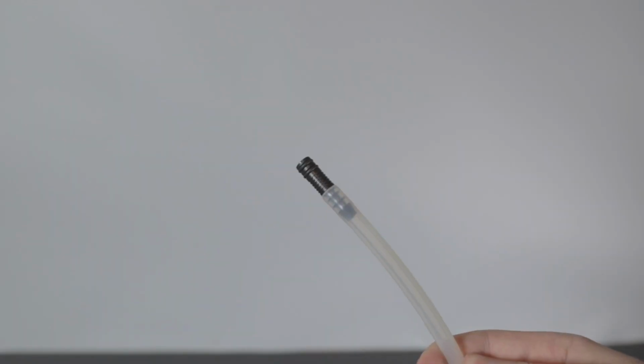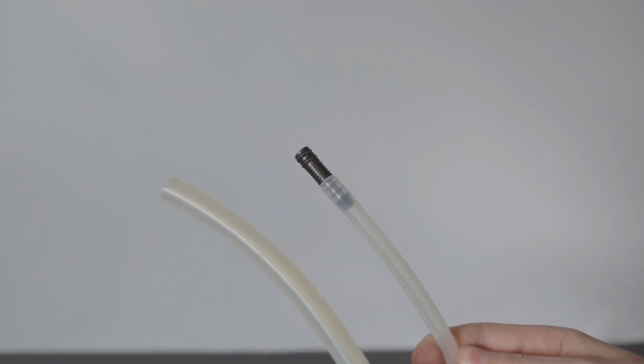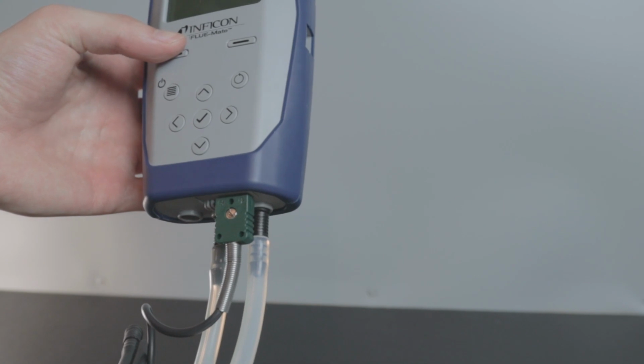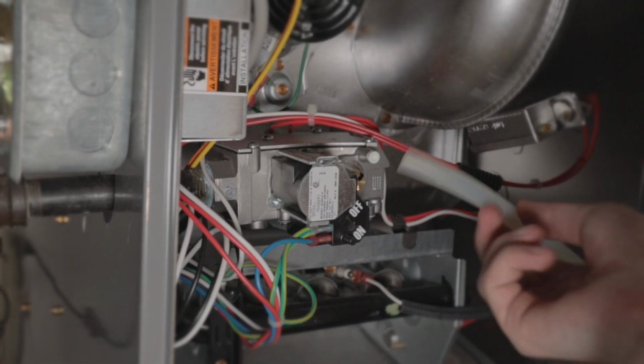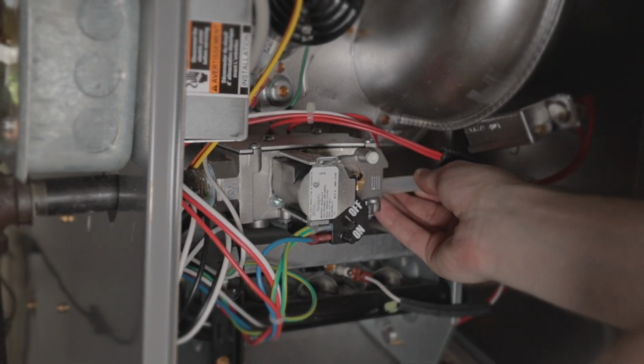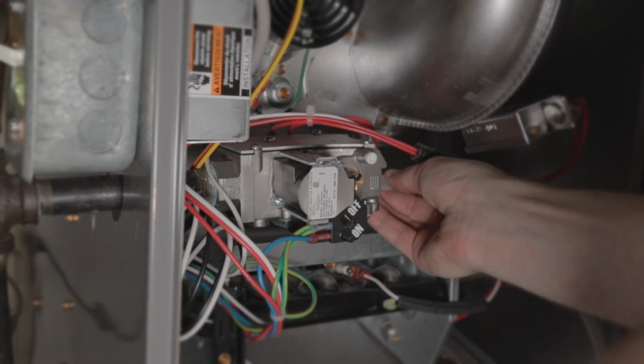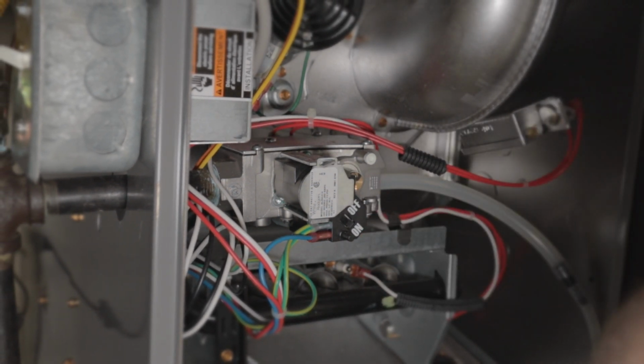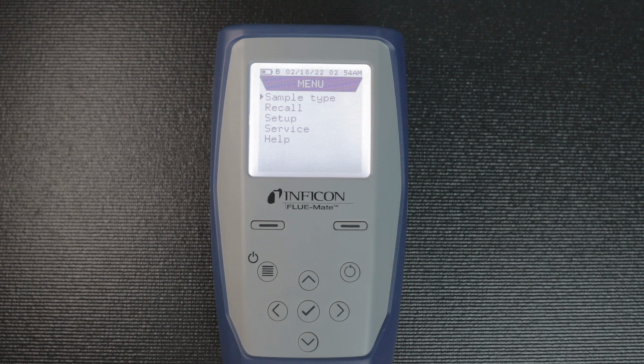The included manometer hose can be used to measure gas pressure. Connect the manometer pressure hose to the P+ port on FLUE-Mate and refer to the furnace manufacturer's operating manual for instructions on how to test for gas pressure. To view the pressure readings, enter the menu on FLUE-Mate, then select Sample Type and then Pressure.